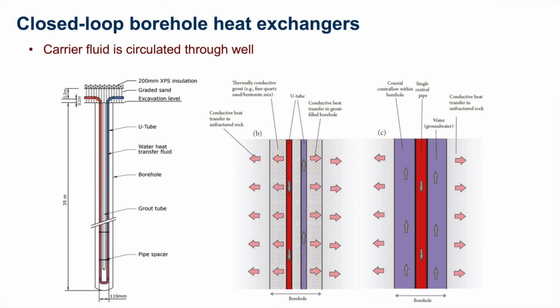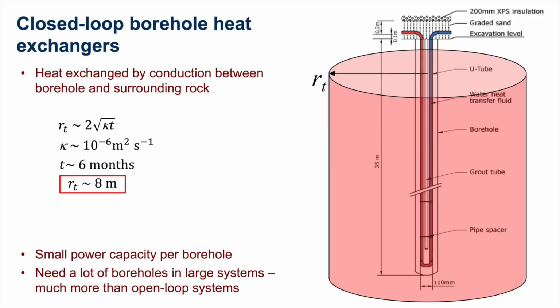A closed loop heat exchanger works on the same basic principle, but now we rely on conduction to move heat in and out of the borehole. We'd typically have a U-loop, injecting down one limb and returning up the other, or a coaxial arrangement injecting down the middle and returning up the outside. We can do a back-of-the-envelope calculation, assuming conduction and about 6 months of heating, to see how far from the well we can get heat or cool. It turns out we only get about 8 metres away from the well.